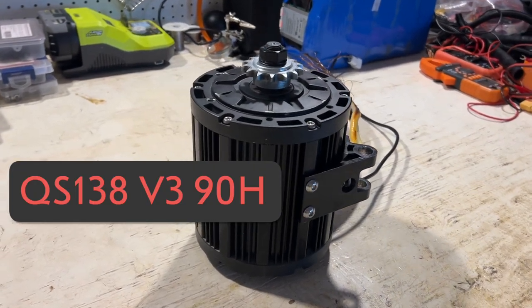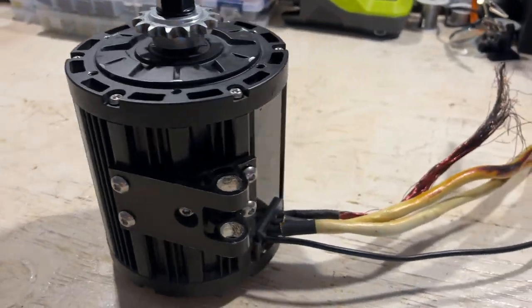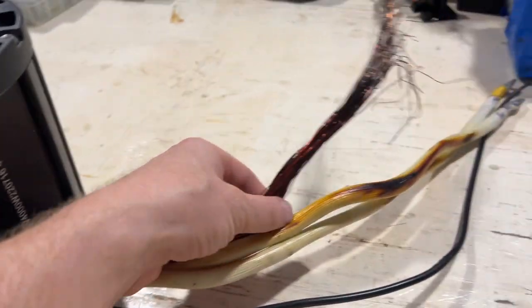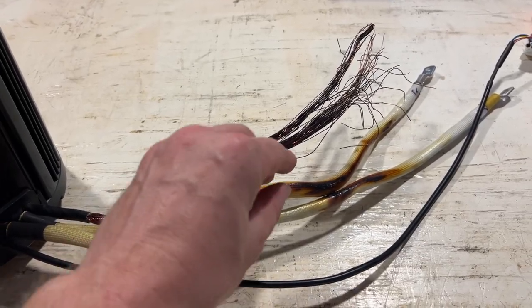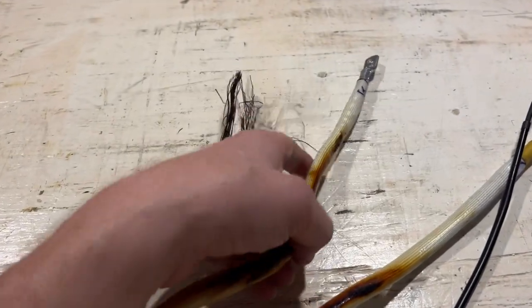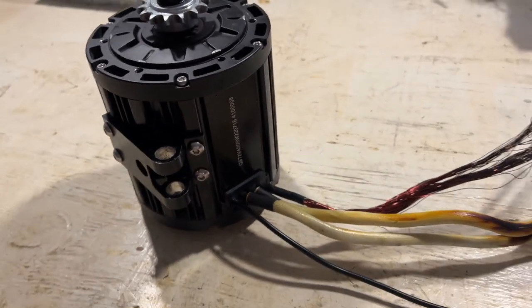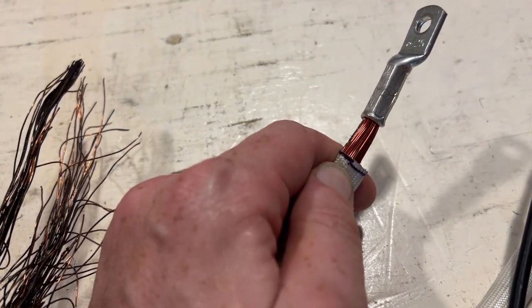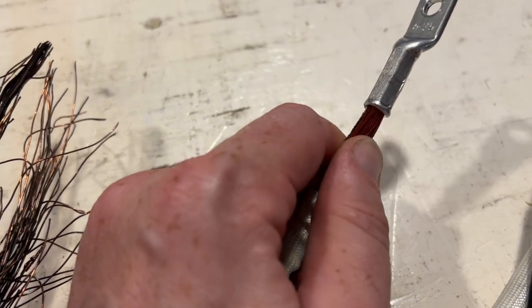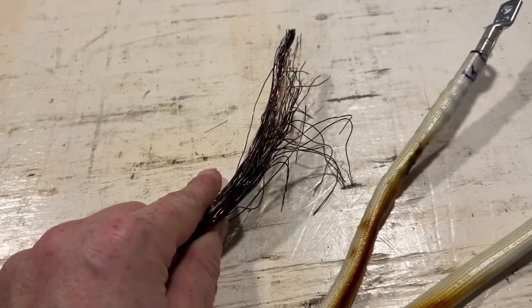Here we have a QS138 V3 90H motor and this motor is damaged. As you can see there was a fire, and the reason for the fire was actually just egregious negligence in terms of quality control on the part of the vendor who sold this motor. Basically they crimped these lugs directly onto the enamel covered phase wires which heated up the phase wires and caused the fire.